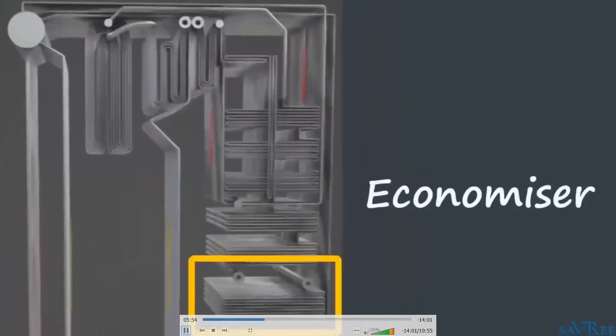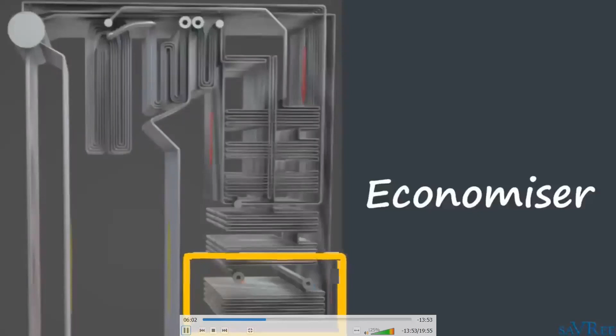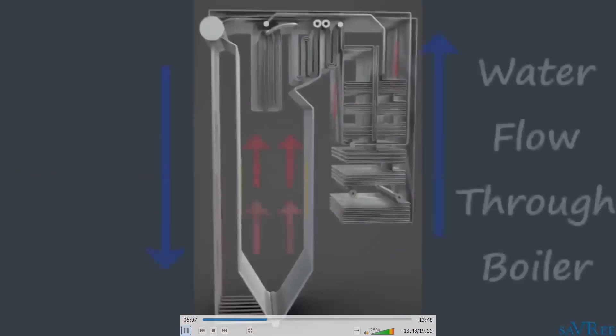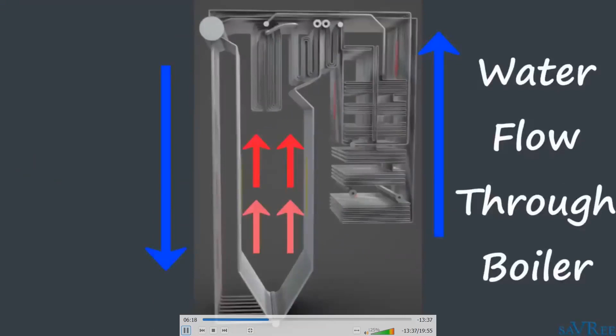We don't want to feed cold water into the main part of the boiler, or the furnace as we call it, because if we do that, then we're going to thermal shock the boiler, and that could mean that we have cracked pipe. The yellow circle is showing the location of the economizer inside the boiler. So we'll preheat the water by sending it to the economizer. We'll then send the water around to the furnace, and we'll put the water into the water tube boiler walls. They're called walls because the piping around the furnace makes up a square space similar to having 4 separate walls.